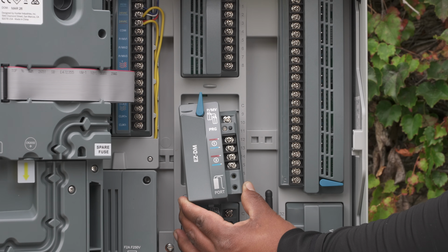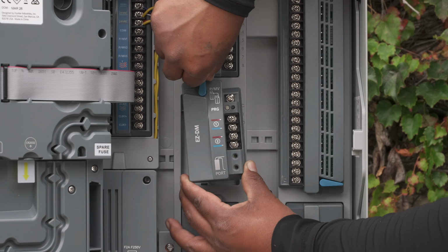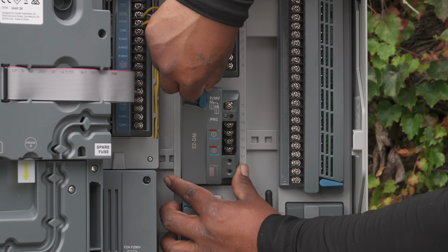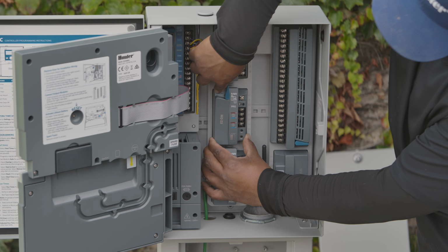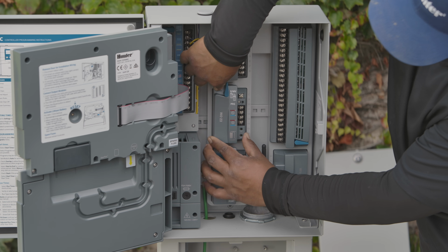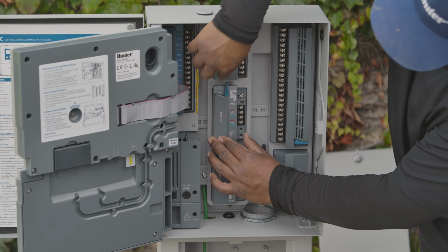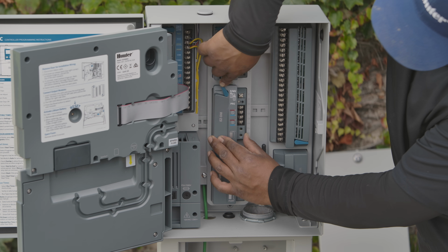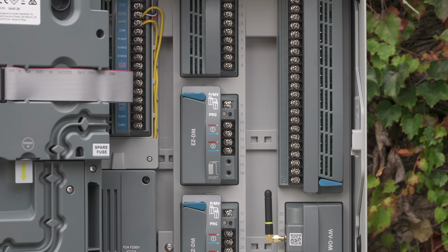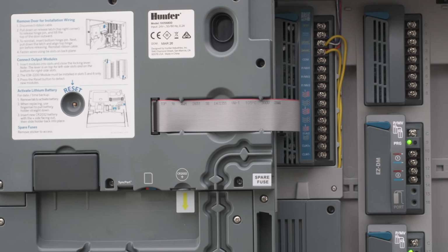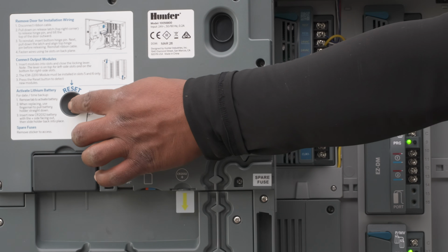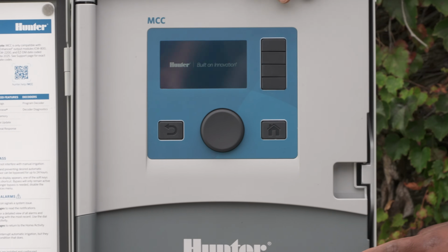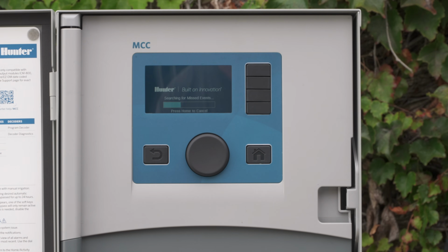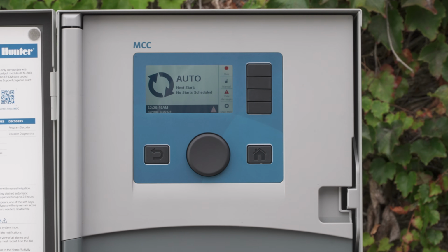To install any of the modules, first, open the blue locking lever. Always insert the little foot into the hole on the bottom or top edge of the slot first. Then, tip into place to connect the pins on the back of the module. Finally, turn the blue locking lever to lock the module in place. The final step after installing your new modules is to press the reset button on the back of the facepack door. This will cause the controller to restart and recognize the new modules and update the total station count.